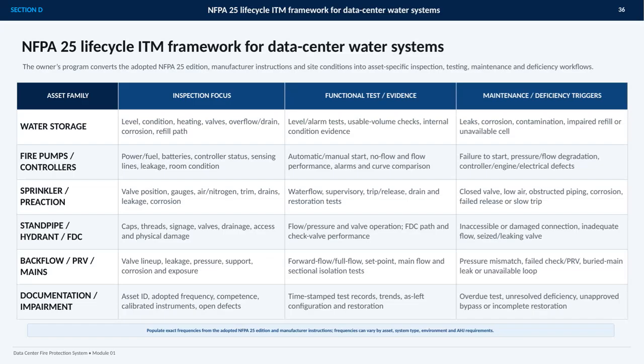This slide translates NFPA 25 into a practical, asset-specific lifecycle program for data center water systems. The owner combines the adopted NFPA 25 edition, manufacturer instructions, and actual site conditions to define inspection, testing, maintenance, and deficiency workflows. The key is to connect every asset to both evidence and corrective action. For water storage, that means checking level, condition, heating, valves, corrosion, and the refill path, then documenting alarms, usable volume, and internal condition. Fire pumps and controllers require power, fuel, batteries, sensing lines, automatic and manual starts, flow performance, and alarm verification.